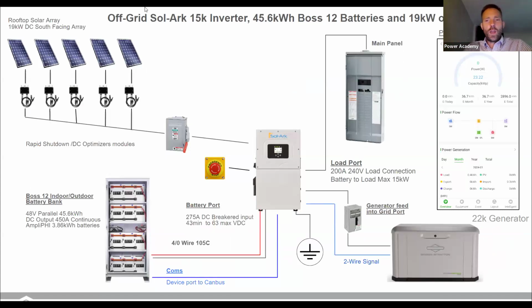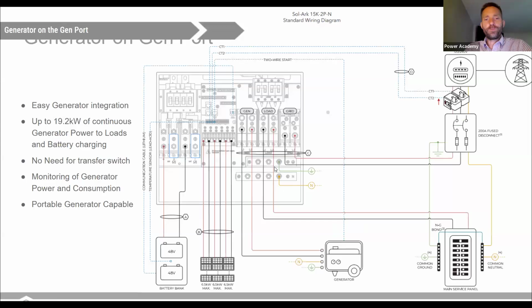So we can do this. We can also add more to this. If we're in a location that has typically very long outages, like maybe somewhere in Florida or Louisiana, where you can get hurricanes that can take power out for a week, you might want to have a backup generator integrated as well. Another really nice thing about that Sol-Ark 15K is you can run off of solar and batteries unless your batteries get down too far, and then the inverter can start up the generator. That generator can then charge up the batteries, shut the generator off quickly so you're not using a lot of fuel, and then you'll run off those batteries again through that main loads panel. And so the Sol-Ark is capable of controlling that generator through a 2-wire start, and I'll talk about how to wire that a little bit later.